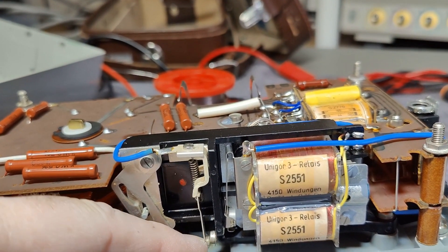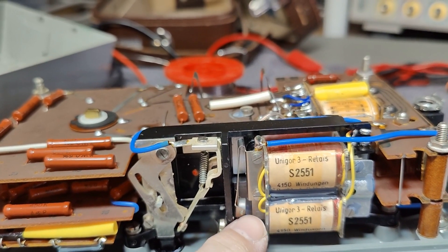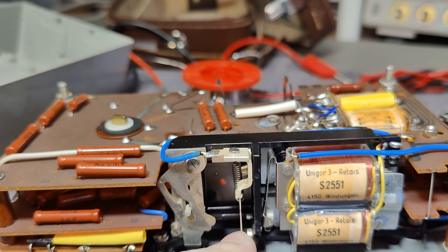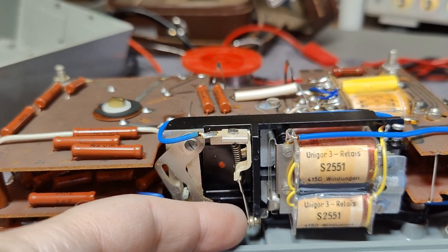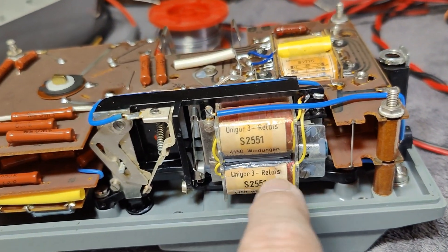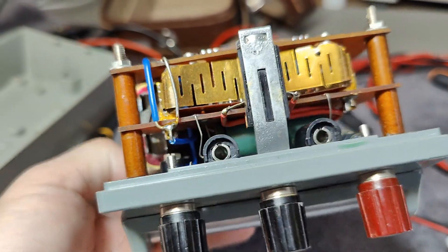The problem is noted — it even says Unigor 3 relays, so they are using the same relay in many different versions. We have a problem with the relay: the magnet here is not so strong anymore. You just barely touch it and it falls back. This spring is very tough, but it is supposed to be tough because it hammers back to the release mechanism. But it actually holds — just barely. I will try and clean this and see what we can do.